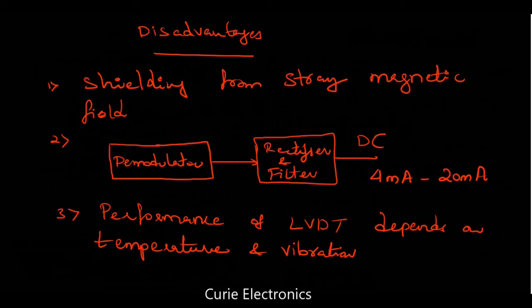Then one more thing, what is the output? Output is AC. For processing this output, modern day microprocessors, microcontrollers, and PLCs need DC. So what we do is use a demodulator, phase demodulator, and a rectifier filter to convert it to DC. This DC can be used, or we can convert that DC signal to a 4 milliamp to 20 milliamp signal, which is more suitable for PLC applications. So it is AC, but modern day processing needs DC.